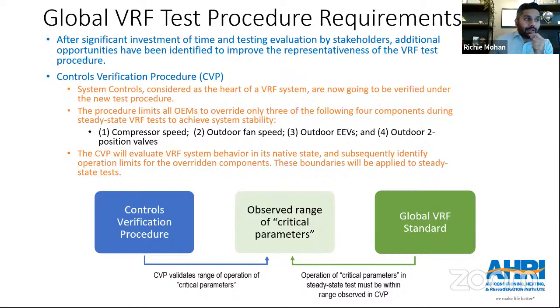Now, as for what the critical parameters are, these are compressor speed, outdoor fan speed, the outdoor expansion valves, and the outdoor two-position valves. These are the only 4 parameters which can be locked in or manually controlled during a steady state test. And these are the 4 parameters which we are observing or monitoring during the CVP. Beyond these 4 parameters, everything else has to be kept free floating, such that the manufacturer cannot lock that setting in, or the lab personnel cannot lock a setting in. You let all of those parameters just run on their own.